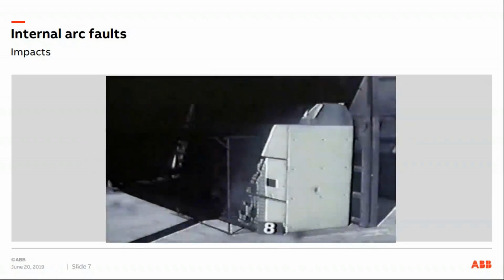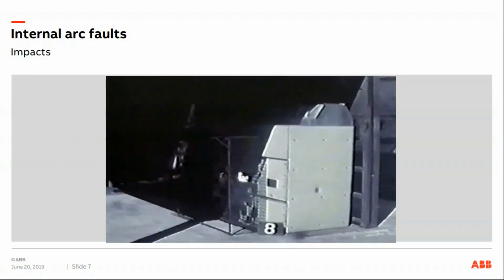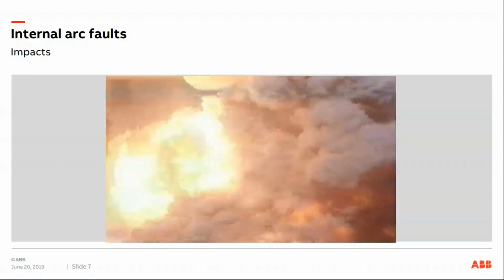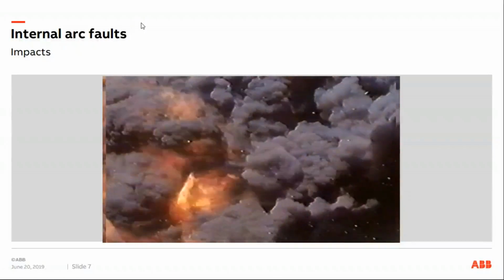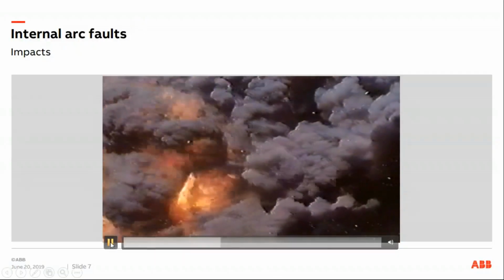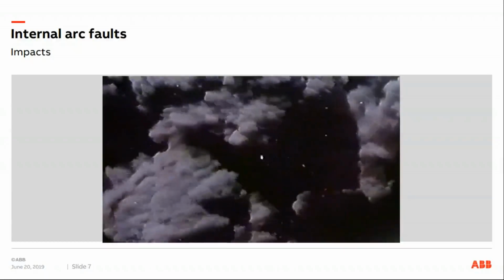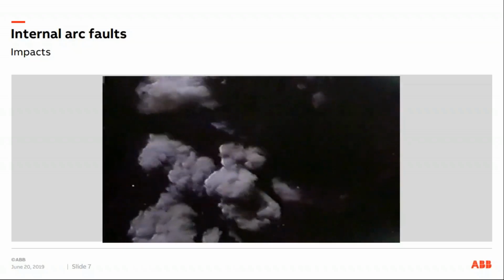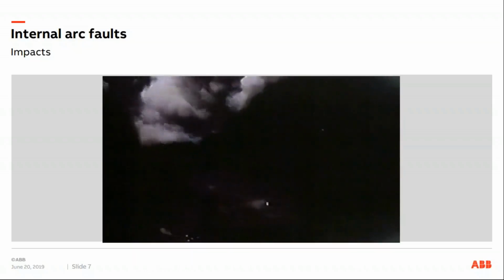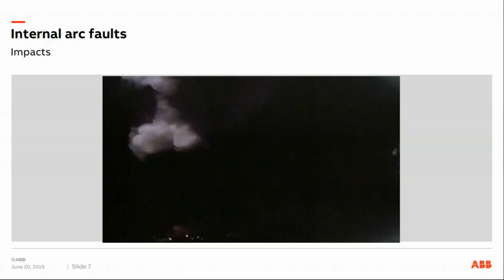Here we see a video. The video you've just watched presented a typical behavior from an arc accident in an actual test performed by ABB. That was an internal arc test for 50 kA, 1 second. Fault initiation was in the circuit breaker compartment.